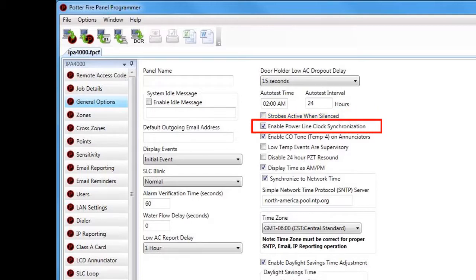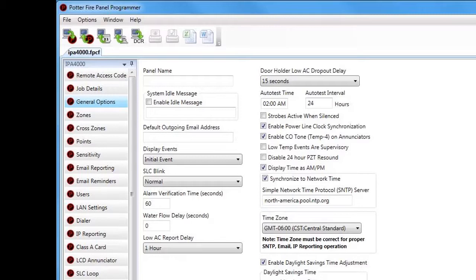Next is Enable Power Line Clock Synchronization. This keeps the clock synchronized to the 120-volt, 60-hertz power circuit coming into the fire alarm control panel. It is recommended to keep this checked unless your power is not 120V or 60Hz. The next option is Enable CO Tone TEMP-4 on Enunciators, which is checked by default. This means that on a CO event, the enunciators — both the fire alarm control panel and any remote enunciators — will sound a TEMP-4 pattern on a CO alarm or CO supervisory event.